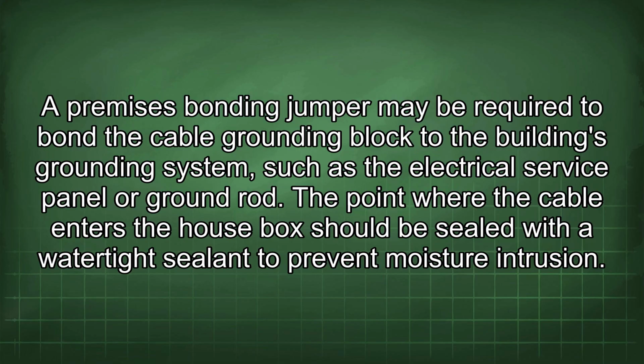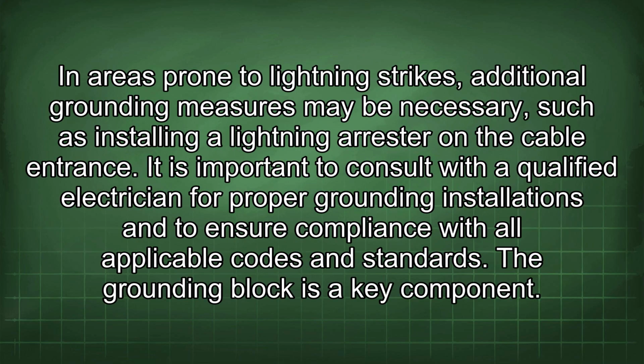The point where the cable enters the house box should be sealed with a watertight sealant to prevent moisture intrusion. In areas prone to lightning strikes, additional grounding measures may be necessary, such as installing a lightning arrestor on the cable entrance. It is important to consult with a qualified electrician for proper grounding installations and to ensure compliance with all applicable codes and standards.